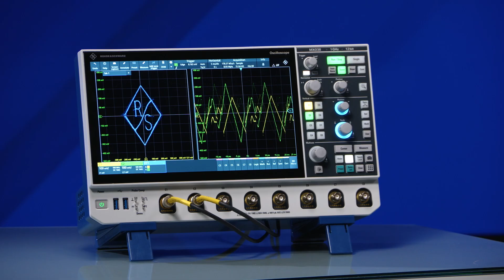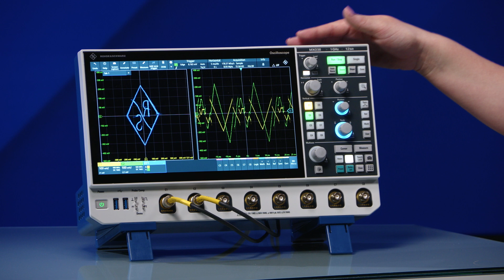In XY mode, one channel is plotted against another channel, not as a function of time. XY mode is typically a special mode on the scope that allows you to select which channels are X and Y. Here you can see that we are plotting the X and Y signals that we are measuring. Set up which channels you want to configure in the menu and enable the capability.